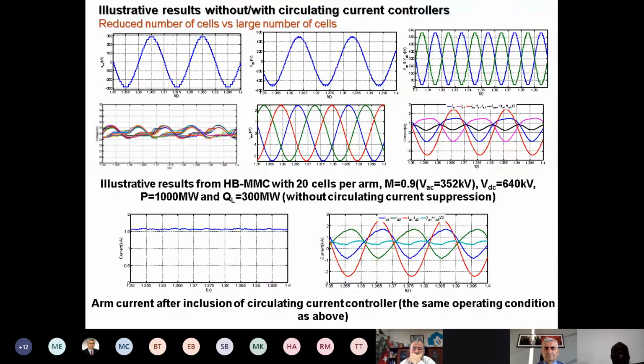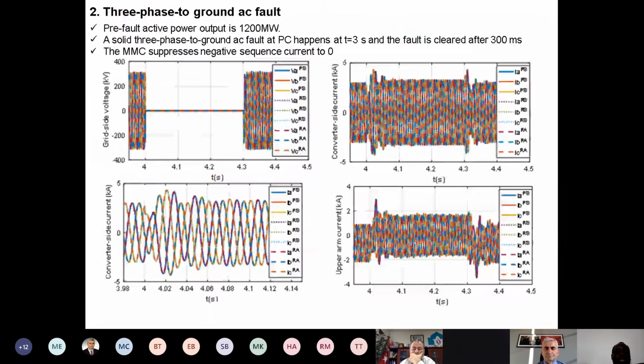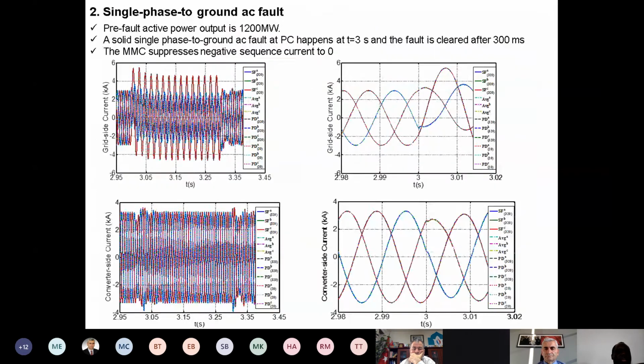This current contains second order harmonics. In this case, the second harmonic will increase the losses, and you will need a bigger capacitor to keep the ripple in the capacitor voltage lower. So to avoid this outcome, we added an extra controller just to suppress that second order harmonics. That also actually helps, this controller also helps in the case of single phase fault.